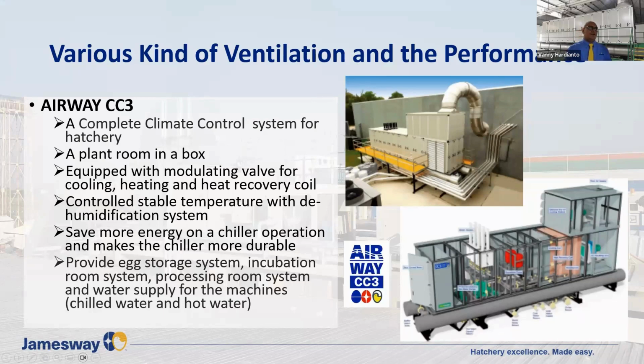A few years back, we introduced a complete climate control system for the hatchery. It's called the Airway CC3. This machine is like a plant room in a box. It's equipped with the modulating valve for cooling, heating, and also for the heat recovery coil, which can produce a more stable temperature and humidity. It's the most important thing from this ventilation system.